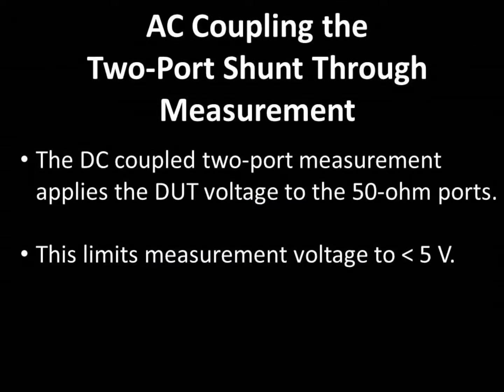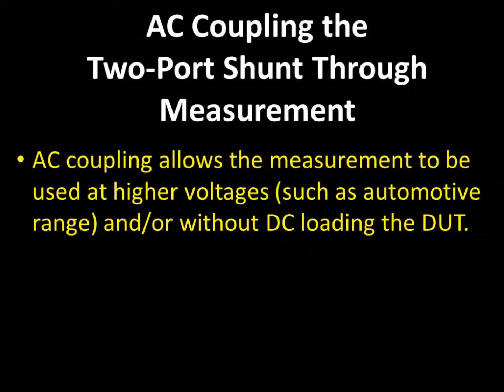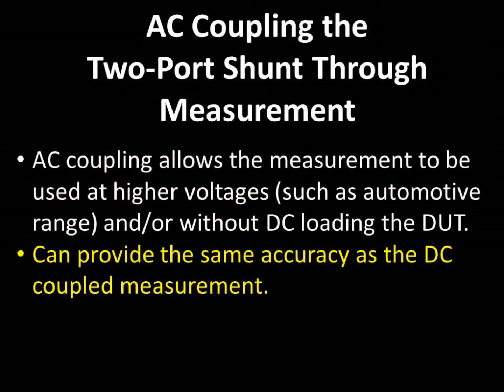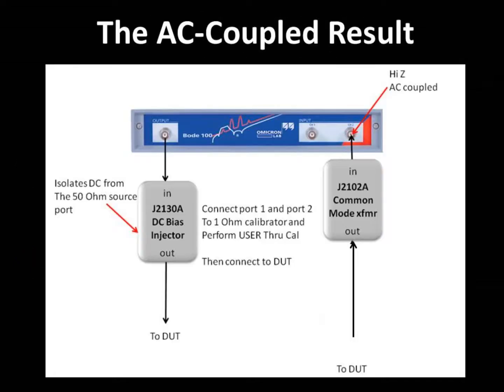In some cases, we'd like to make the two-port measurement at higher voltages. This is often the case in measuring battery impedance and output impedance of intermediate bus converters, input impedance of any DC-to-DC converter, or EMI filter stability. It's possible to AC-couple the two-port measurement, allowing measurement at higher voltages with the same accuracy as the DC measurement. In order to AC-couple the measurement, at least one DC blocker, such as the J2130A, is required. The DC blocker is required at the port 1 or oscillator side of the measurement. The port 2 channel, using the FRA mode, can be set as a high-impedance AC-coupled port. As in the case of the DC-coupled measurement, the common mode transformer is still required, unless the analyzer has a semi-floating or floating front end.